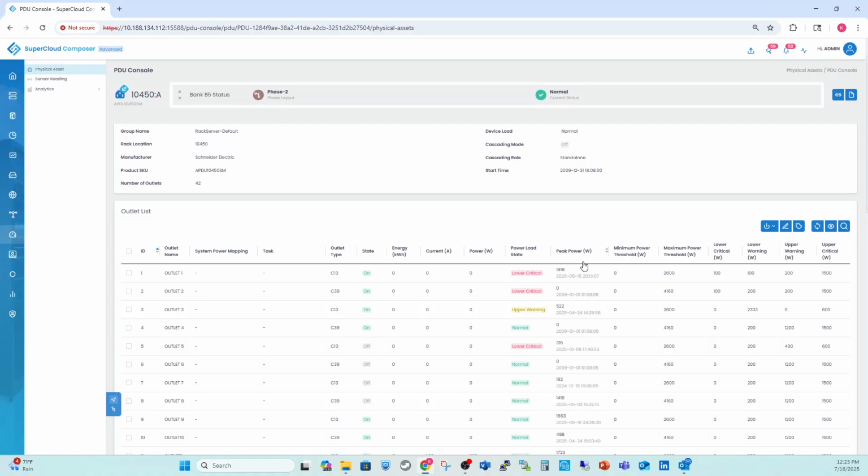So you ask, well, gee, Kevin, why do we provide threshold settings for the PDU? An important thing about that is to be able to send alerts when you've reached certain threshold settings so that you can alert on it and perform action. Perhaps you've overloaded a PDU and you want to get an idea of how much current or load is running associated with that PDU or what the peak power is. So these are all important analytics data that you need to pull from a PDU.